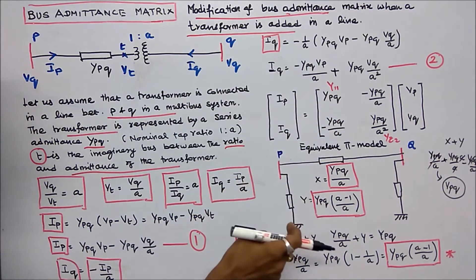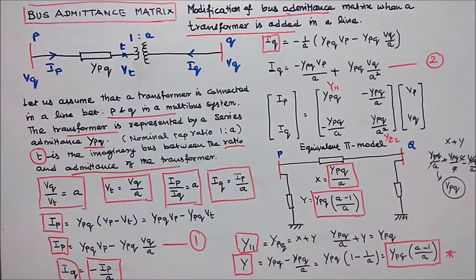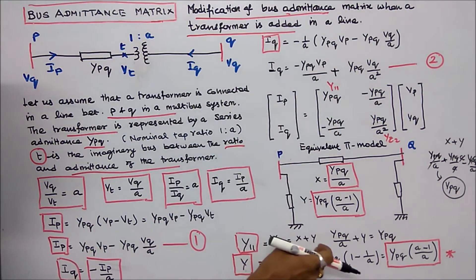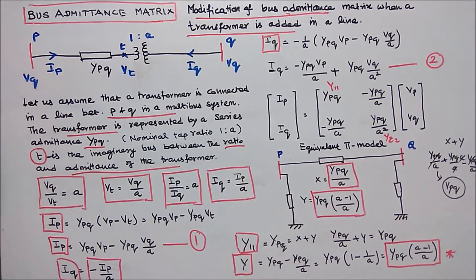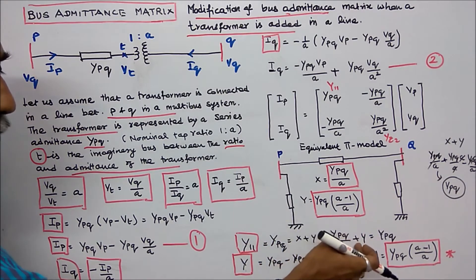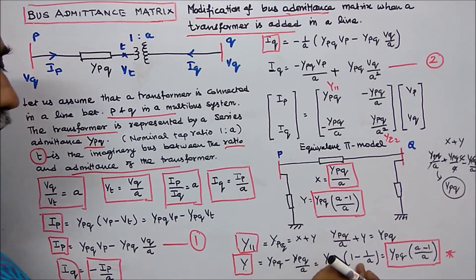This is an equivalent pi model for a tap-changing transformer. Here Y11 is equal to this admittance plus this admittance, so Y11 equals YPQ. I choose X equal to YPQ divided by A. Then YPQ divided by A plus Y equals YPQ, so Y equals YPQ minus YPQ divided by A, which equals YPQ multiplied by (1 minus 1 divided by A).